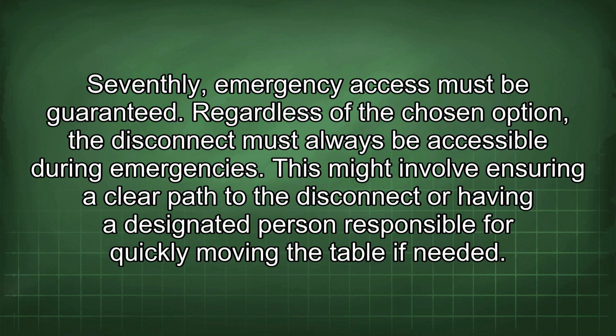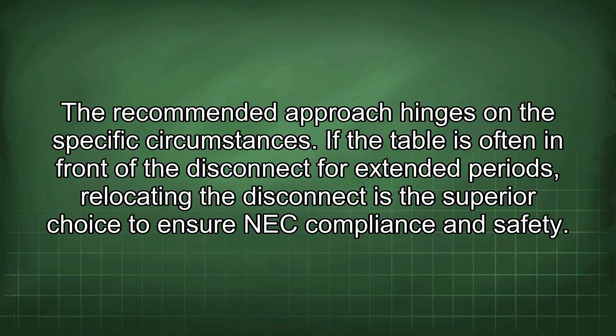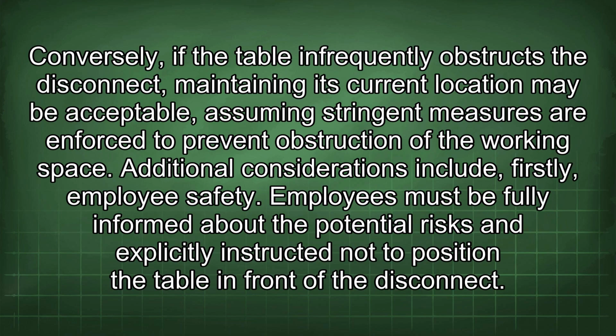Regardless of the chosen option, the disconnect must always be accessible during emergencies. This might involve ensuring a clear path to the disconnect or having a designated person responsible for quickly moving the table if needed. The recommended approach hinges on the specific circumstances. If the table is often in front of the disconnect for extended periods, relocating the disconnect is the superior choice to ensure NEC compliance and safety. Conversely, if the table infrequently obstructs the disconnect, maintaining its current location may be acceptable, assuming stringent measures are enforced to prevent obstruction of the working space.